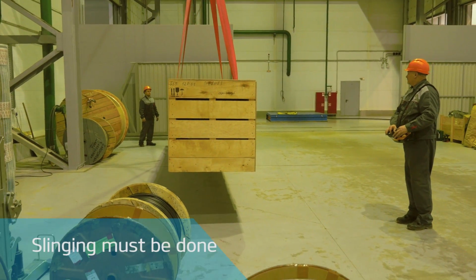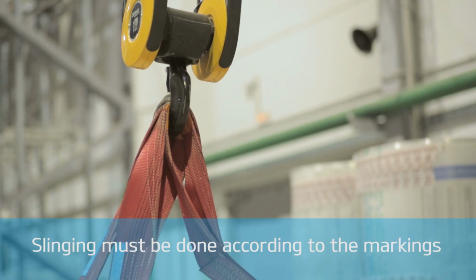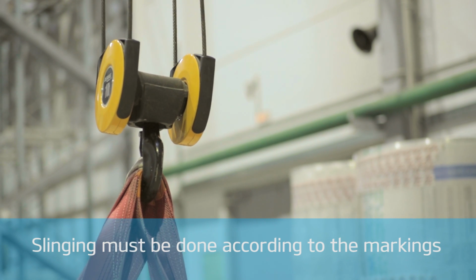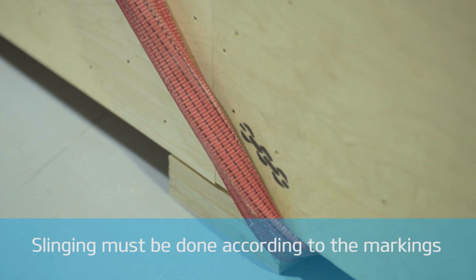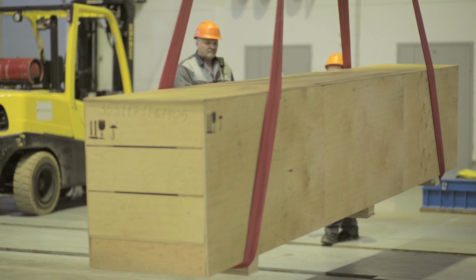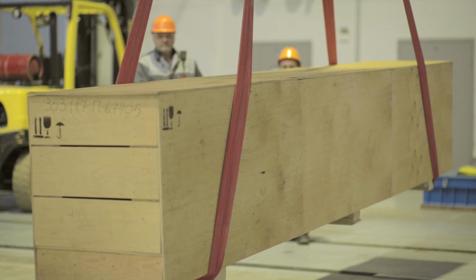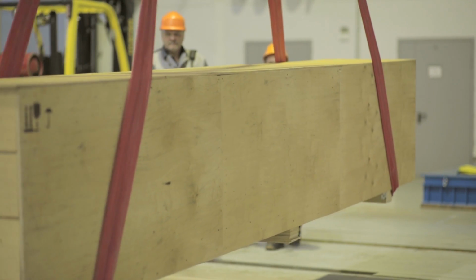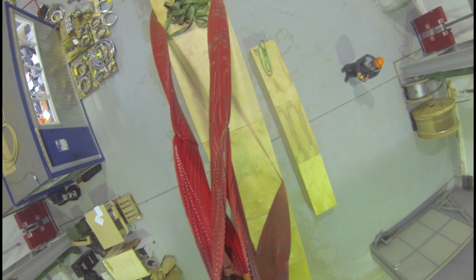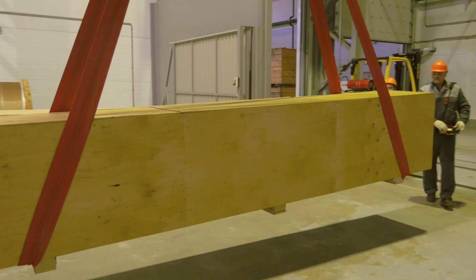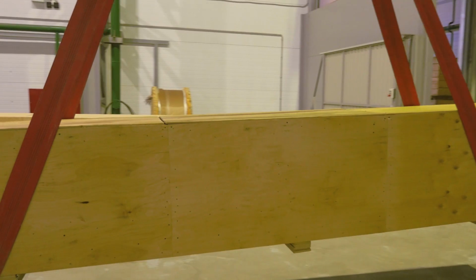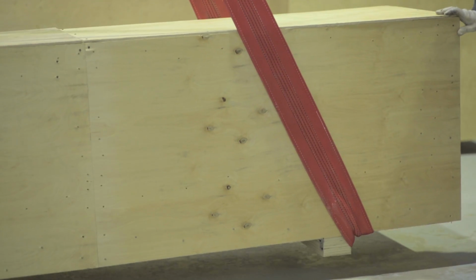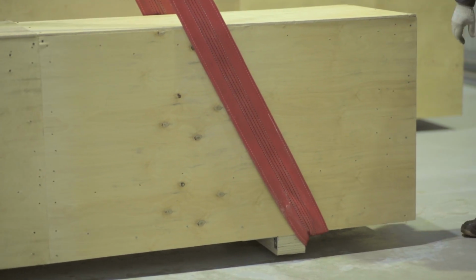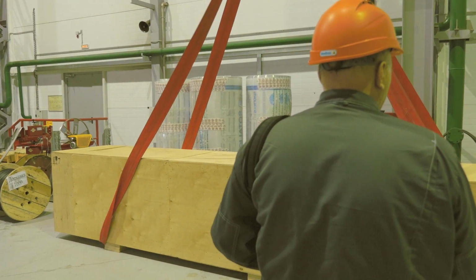Slinging of a bushing packaging must be done according to the markings on the side of the box. To tie up the packaging, pass the cargo rope under the bottom of the box and set it on the hook from one side and then from the other. Lift the box from the floor slightly and make sure it is balanced. Only then any handling of the package can be done.